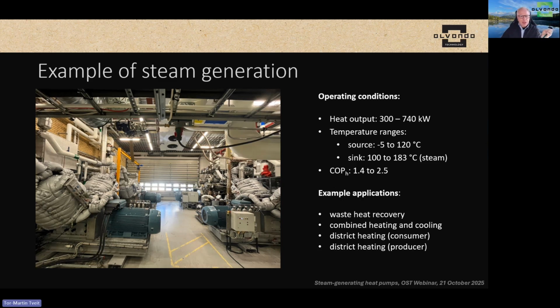Our heat pump has an output range of 300 to 740, 750 kilowatts. Temperature ranges: the heat source can be from about -5 to 120 degrees, and the sink can be from about 100 to 183 degrees. The COP depends, of course, on the temperatures, and it's about 1.4 to 2.5 depending on conditions.